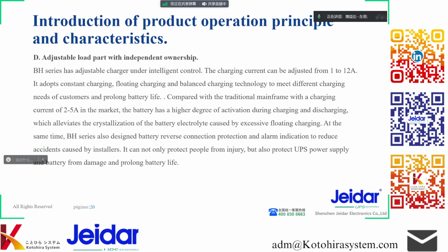Adjustable charging part with independent ownership. The BH series has adjustable charging under intelligent control. The charging current can be adjusted from 1 to 12 amps. It adopts constant charging, floating charging, and balanced charging technology to meet the different charging needs of the customer and prolong battery life. Compared with the traditional mainframe with a charging current of 2 to 5 amps in the market, the battery has a higher degree of activation during charging and discharging, which reduces the crystallization of the battery electrolyte caused by excessive floating charging.